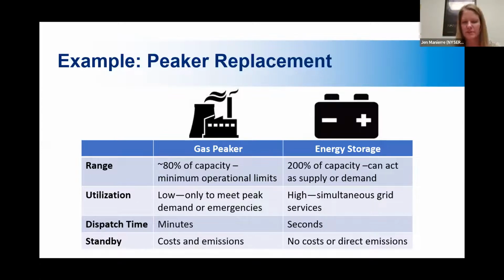on hot summer days. The problem with gas peakers is that they are typically only operating at about 80% of their capacity, and they have minimal operational limits. You can't just run them at a very low threshold, right? Their utilization rate is low. They're only turned on to meet peak demand or emergencies, like I was describing, those super hot summer days. They can take a few minutes to ramp up and dispatch them.